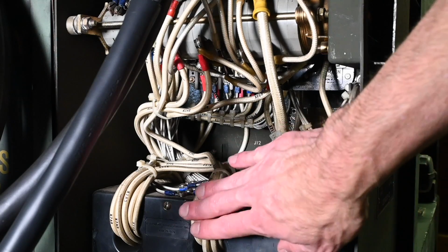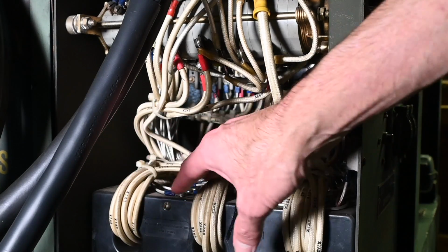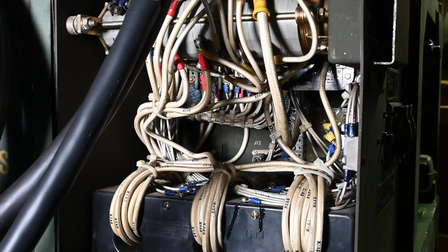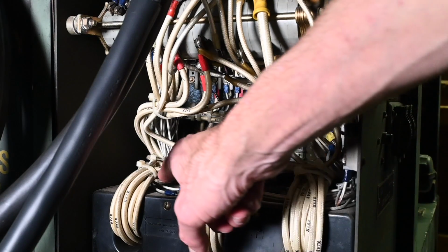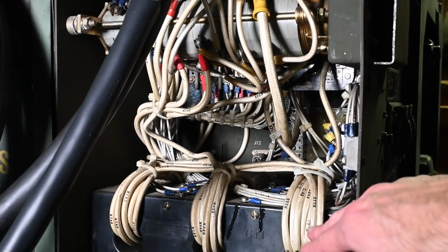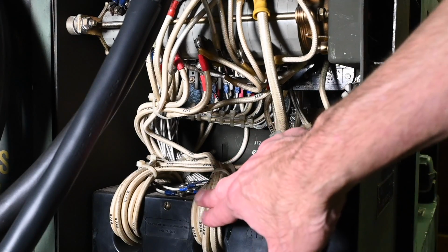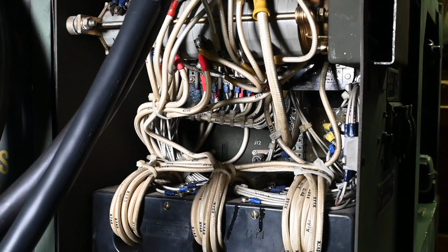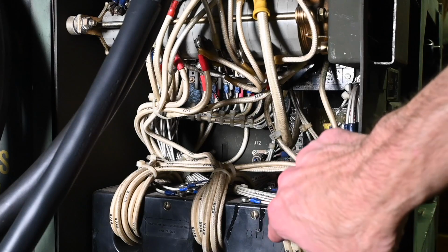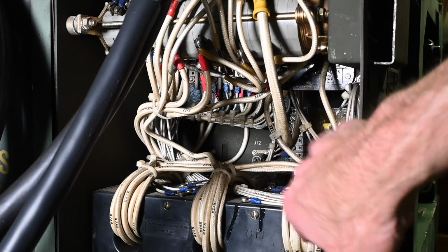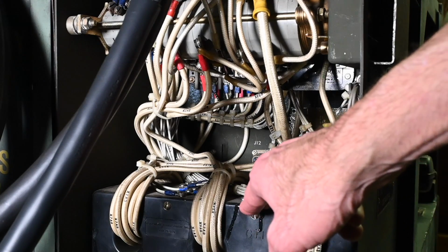So the purpose of this front section of this large device is to generate an output voltage on these terminals and these small wires up here that's in proportion to the current flowing through these large loops of wire. It is used to drive the instrumentation on the front panel to show the load connected on the load meter, and it also is used to trip the circuit breaker if there's an overload. Now, something to keep in mind is that on current transformers like this, you never ever want to allow current to flow through these large wires with nothing connected to the secondaries.